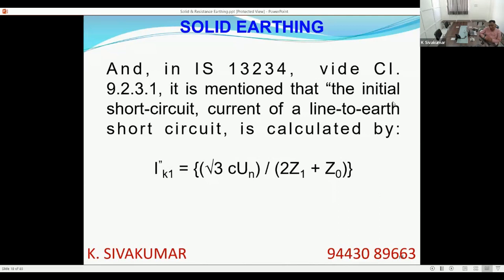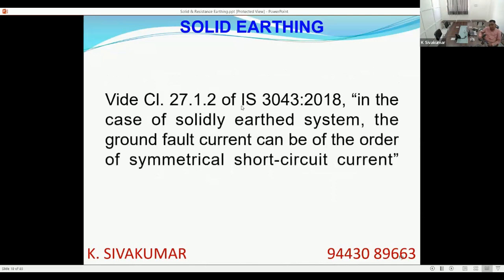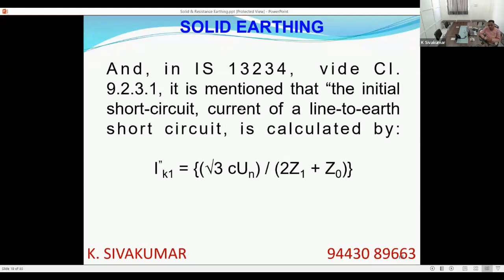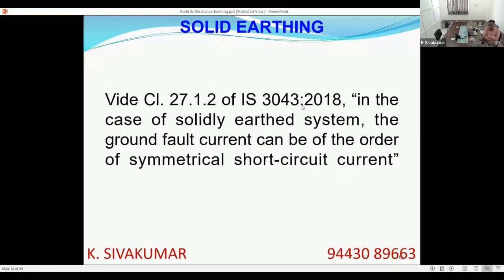Also, many times Z0 is almost equal to Z1 in many cases, except in some transformers, where the manufacturer will give the value of zero sequence impedance, which you can collect. In one more clause, IS clearly says that assuming Z0 is also close to Z1 and Z2, this formula becomes 3 Z1. That means UN by √3 Z. UN by √3 is the phase voltage, and phase voltage by Z is the symmetrical short circuit fault current formula. So the Indian standard very clearly mentions that in a solidly earthed system, the ground fault current can be of the order of the 3-phase symmetrical short circuit current. That means when there is a 3-phase fault in the system, the single phase line to ground fault current, the earth fault current, will be equal to the 3-phase fault current. That is very clearly mentioned in the Indian standard.